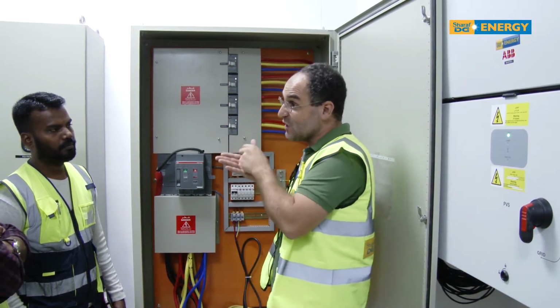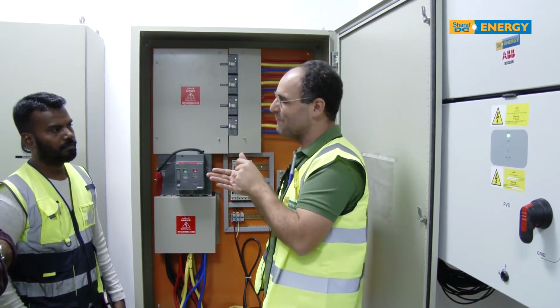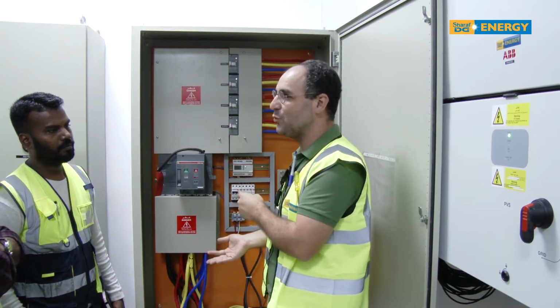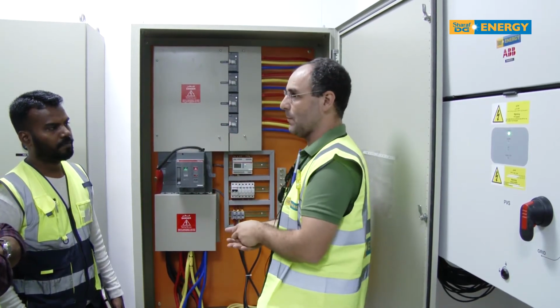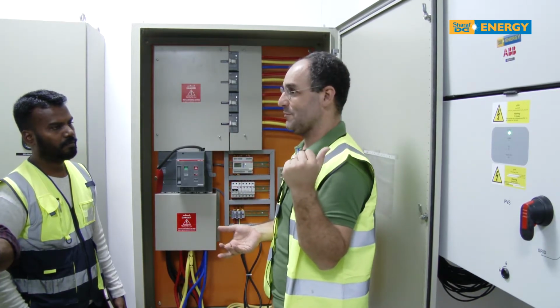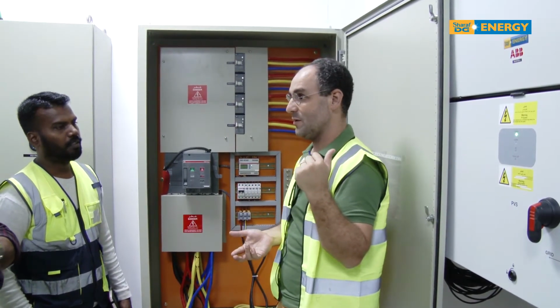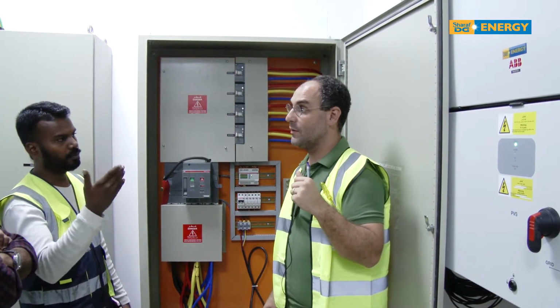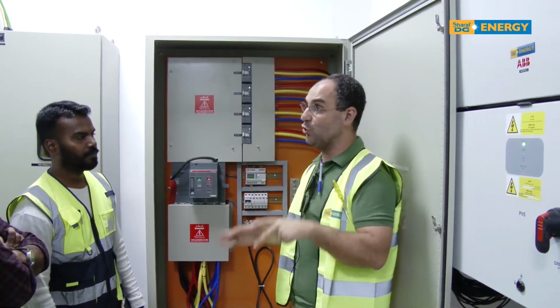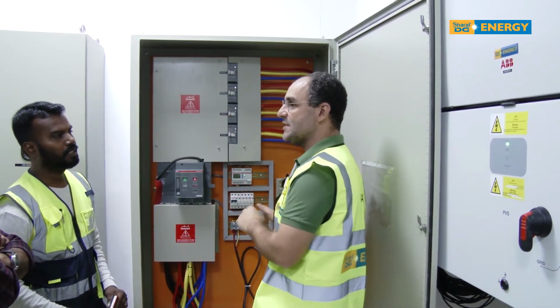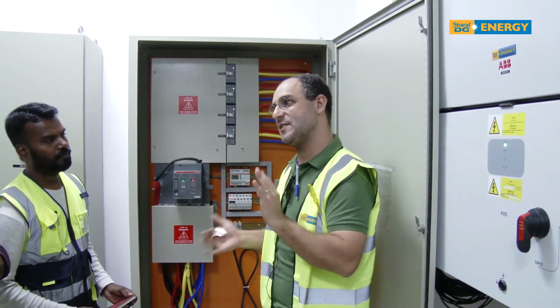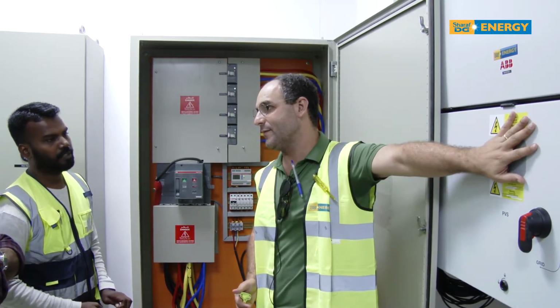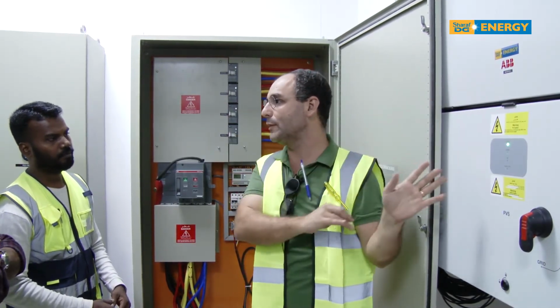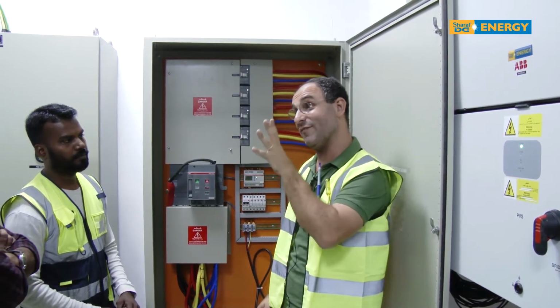Okay? If it shows an alarm, could be multiple reasons, but usually what we do is we hook the computer here, we see the source of the alarm, and then the source will tell us if it is a DC input, or if it's an AC input, or if something else is happening, then we address that problem. Usually it could also be inverter problems, machine problems. All these problems we can go through in the systems. Exactly. What we usually do is just make sure that our DC side and AC side are okay. Because if there are no problems on the DC side and AC side, you cannot touch anything here. You see, take it, put a new one.